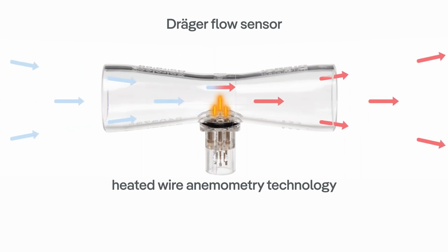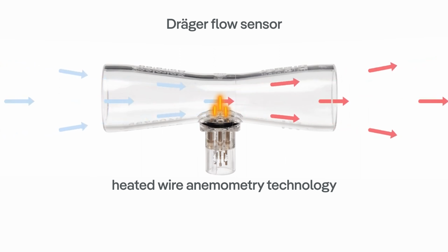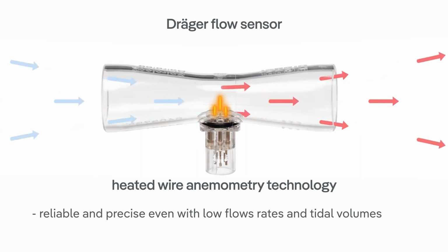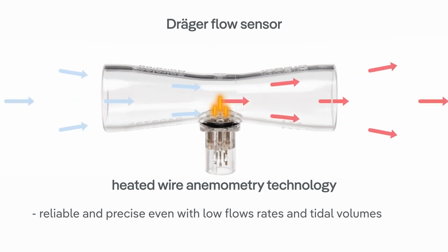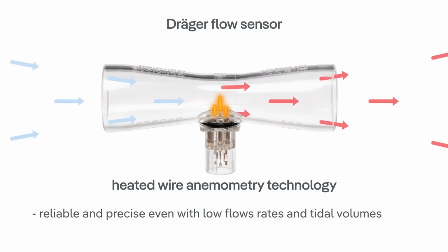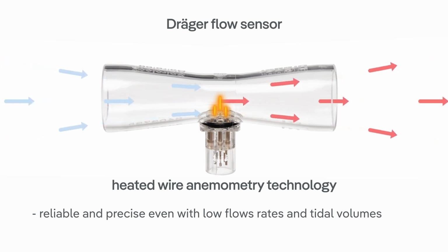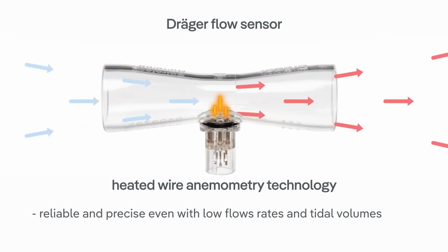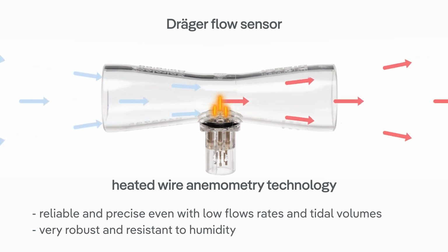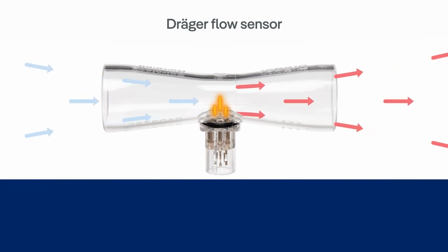Dräger devices use flow sensors with heated wire anemometry technology, which has been proven as very reliable and precise even with low flow rates and thus low tidal volumes. Due to this technology, the Dräger flow sensors are very resistant to humidity and condensation.